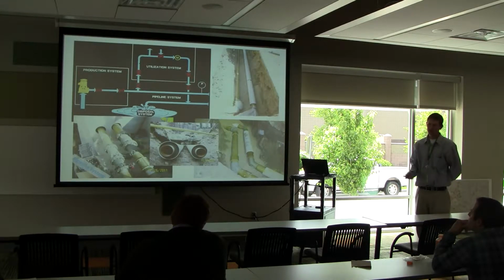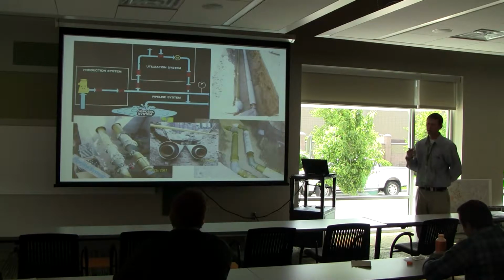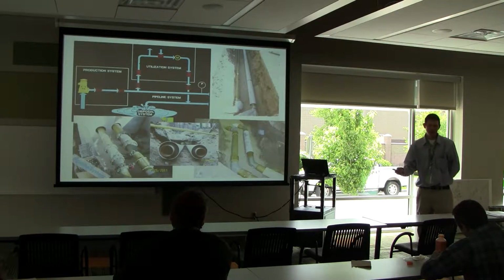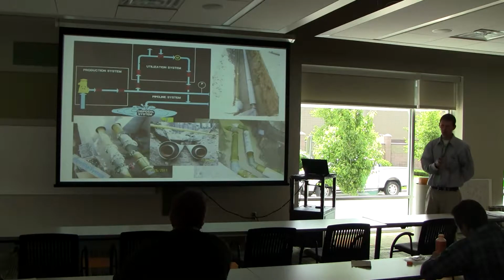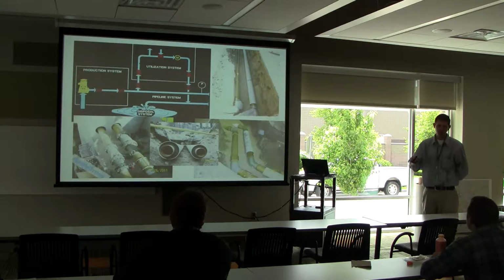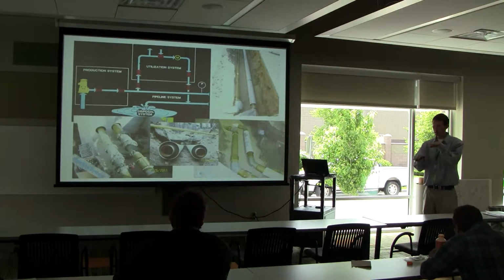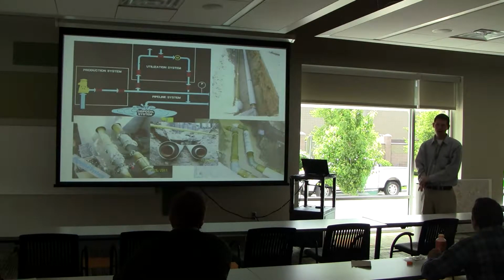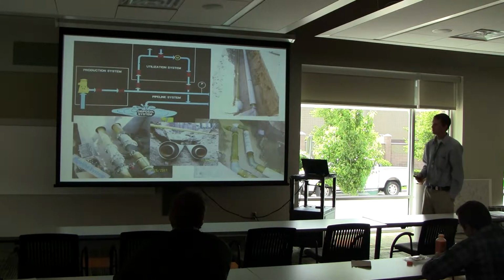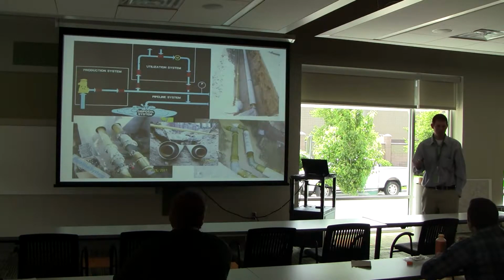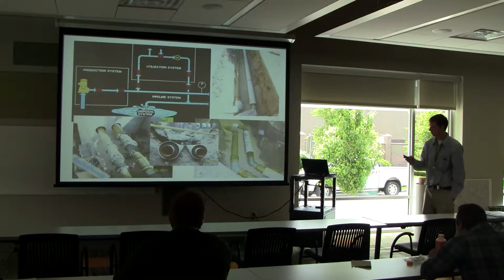We tell businesses that you'll probably receive water at about 160, 165 degrees, though at times it's much hotter. We set our rates based on taking 50 degrees of heat off that water, which makes this a cheaper heating source than natural gas, our current cheapest heating source. Historically the city shadowed natural gas with a 30% differential, but in the last decade natural gas prices have plummeted, so it's been hard to compete. Right now we're at about 5% savings from natural gas, depending on usage and the time of year on different tiers.